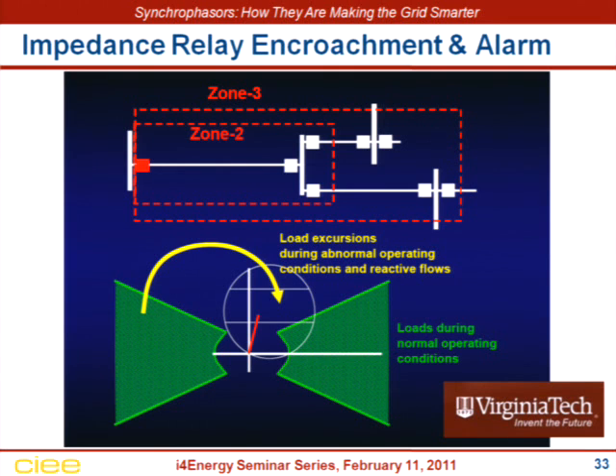Now the problem with these zones is they're fairly big, and this is basically a resistance versus impedance or inductance plot. This is the zone of the relay. And normal conditions all have, this essentially is the system impedance seen by that relay, looking back into the system from its vantage point. Normal conditions are out here and out here. Give me plus flow, minus flow.